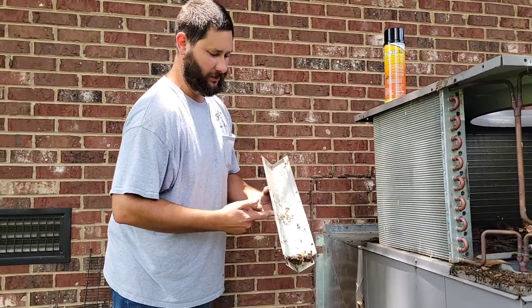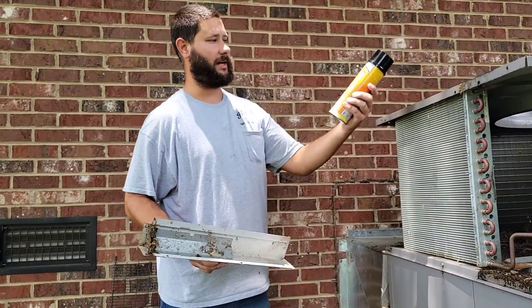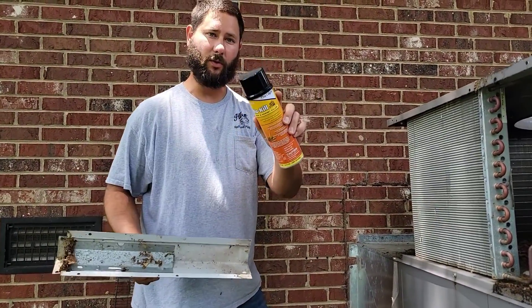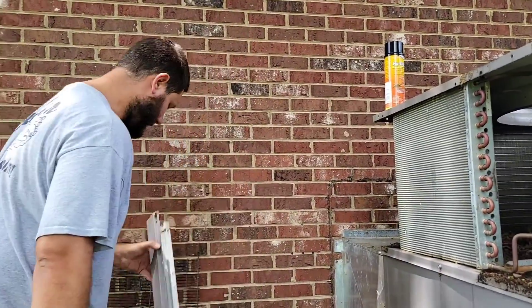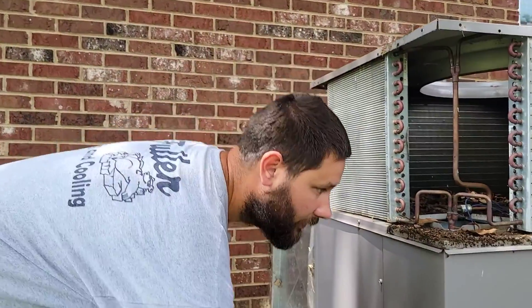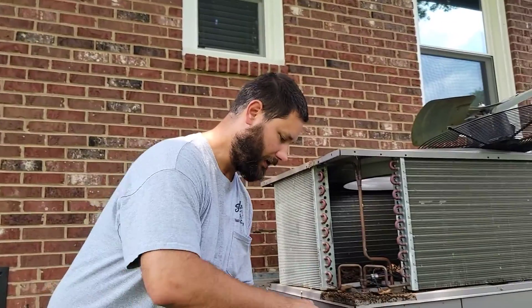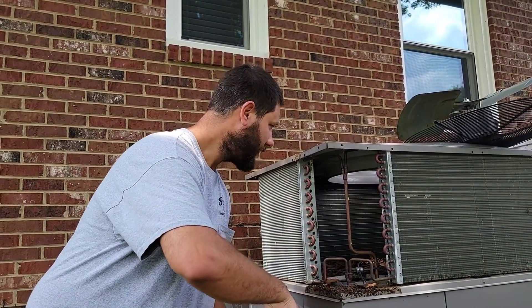Always look inside these corner panels before you remove them because there could be a wasp nest. If there is one, you can use Nu-Calgon's Nu-Kill — this Wasp and Hornet Killer. This stuff is great. Now I've got all the corner panels removed, the fan out of the way, and my water hose connected to my nozzle sprayer. Now I'm going to do a pre-rinse on the coil, remove all the leaves, and get ready for the coil cleaner.